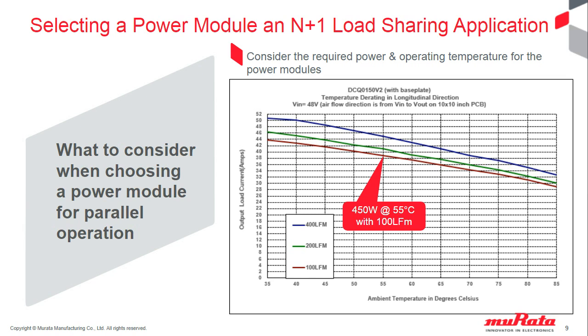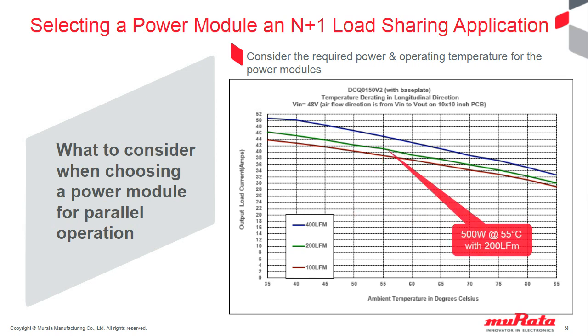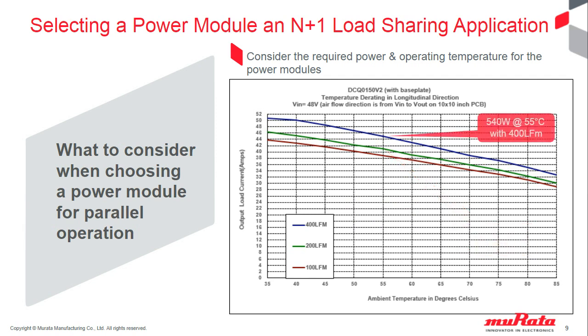Increase that airflow to 200 linear feet per minute, and the module is capable of 500 watts. Again, increase the airflow to, let's see, 400 linear feet, and now the module is capable of 540 watts at 55 degrees C with 400 linear feet per minute. Of note here should be that these tests in many of the data sheets, competitor data sheets, are the same. These are tested with only the base plate. Okay? When you add an additional heat sink to the module, this further improves the thermal derating, and we'll get into that a little later.